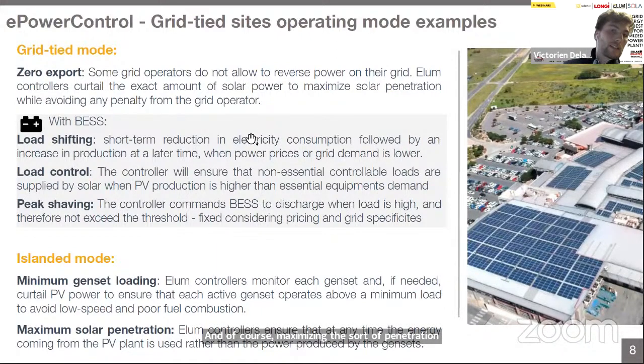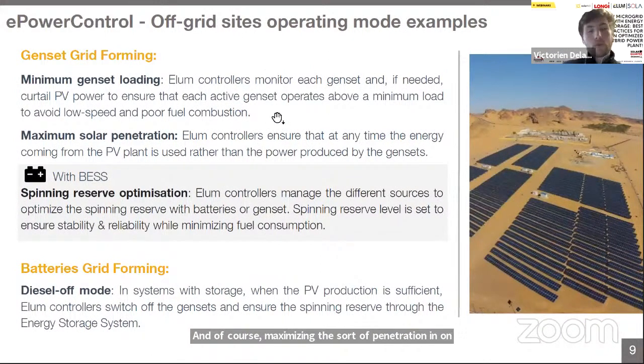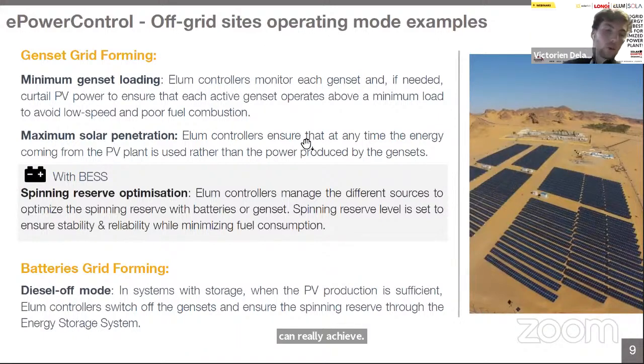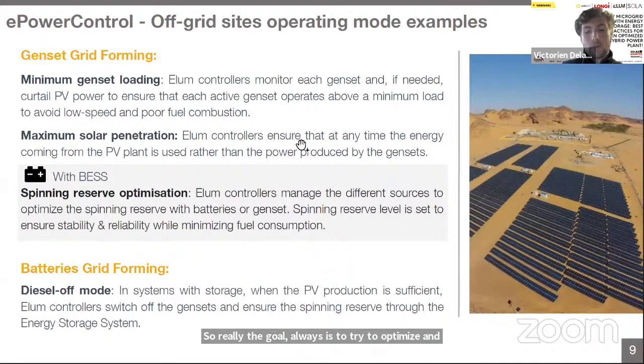And on sites that are totally off-grid, we do the same kind of features that the controller achieves in islanded mode for grid-tied projects: always minimum genset loading, maximum solar penetration. We can also implement -- and that's also the value of having energy storage systems on a project -- nice spinning reserve optimization. So really the goal always is to optimize and get the maximum penetration from renewables, and of course save fuel, save money.